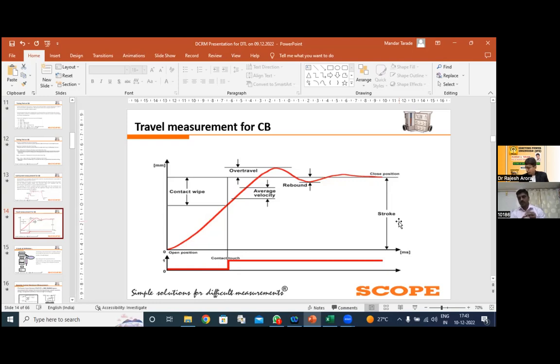at that time we need to keep in mind how we are placing the transducer. A transducer is basically a device which converts one form of energy into another form, that means one form of the parameter into a suitable electrical quantity. So whenever we are placing the transducer on the mechanism, that placement should be proper. At that time, the electrical stroke length value, which we need to feed at the time of doing the calculation, plays a significant role, because we are equating that electrical stroke length value to the applied voltage.